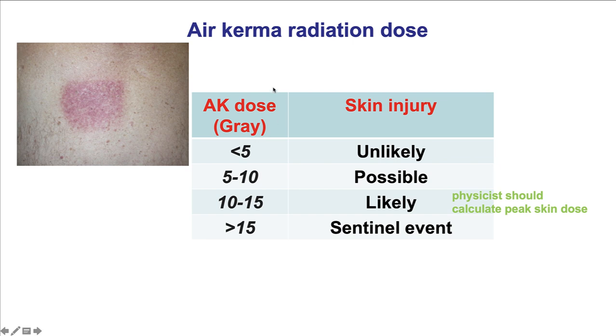How much radiation does it take to create such an injury? Well, it depends on the patient and the entry angle, but these are some common thresholds using the air kerma radiation dose, AK. If it's less than 5, radiation skin injury is unlikely. Between 5 and 10, it's possible. Between 10 and 15, it's likely. And more than 15 is a sentinel event that requires reporting to the regulatory authorities in the United States within 24 hours.